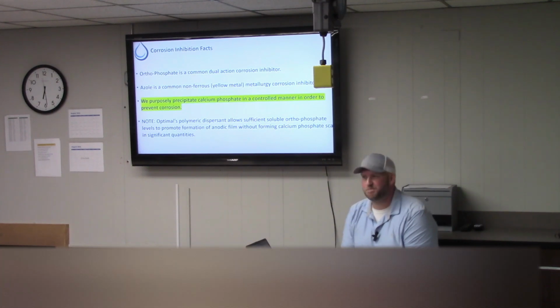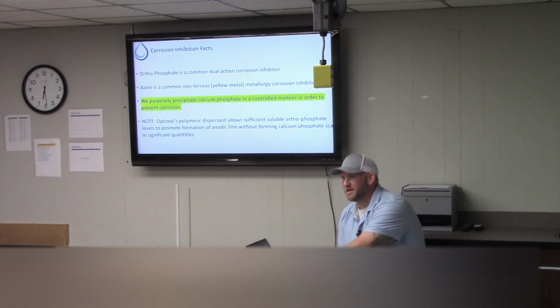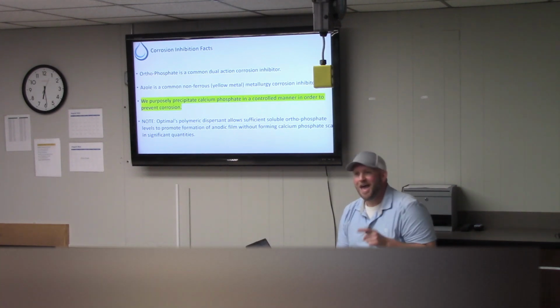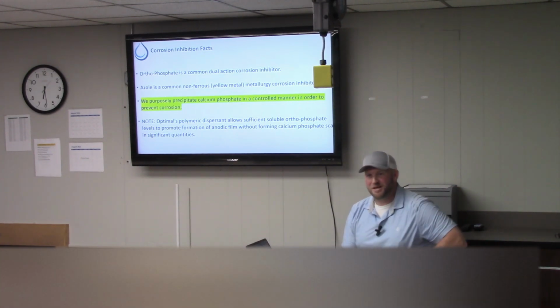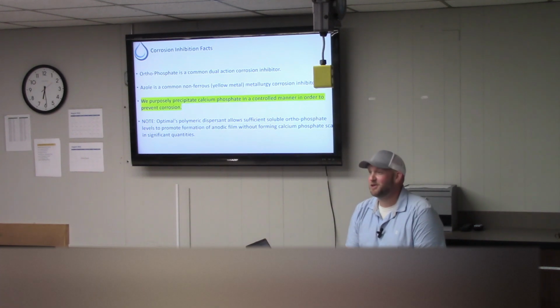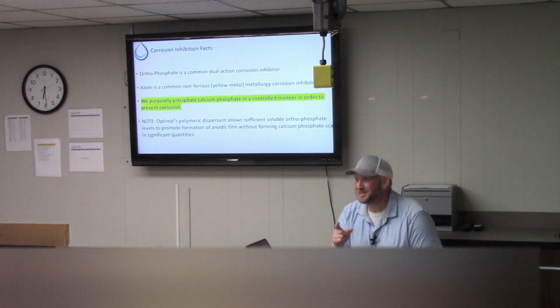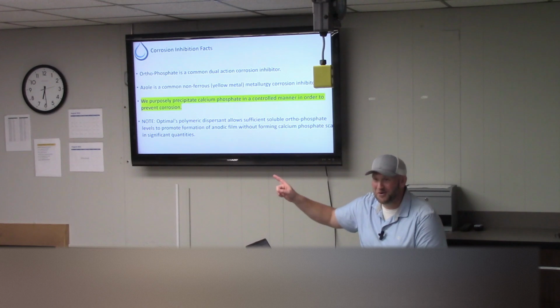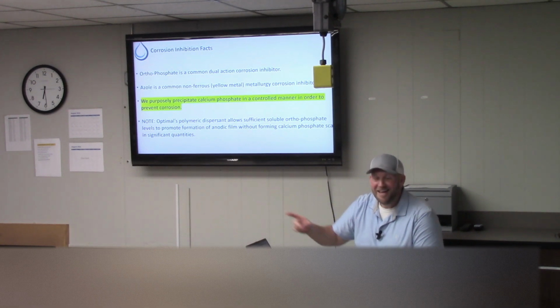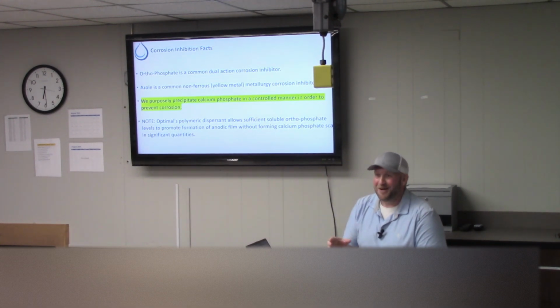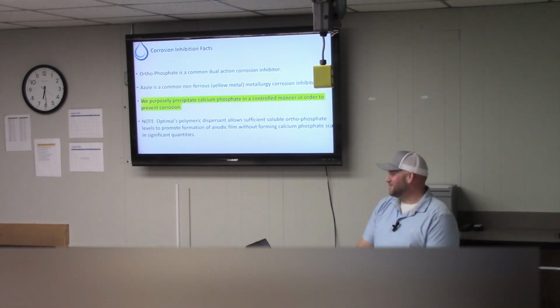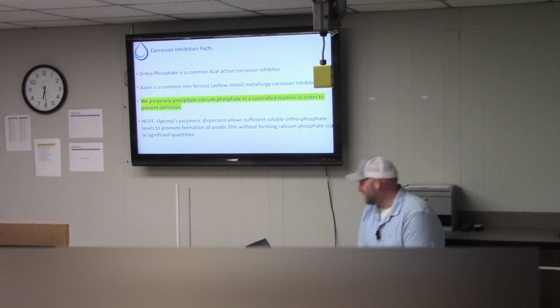They should not be pristine at the end of the year. You should have to do annual cleanings on your cooling tower. And if you do have a pristine basin, you should be asking yourself why, because all that schmooey is setting up somewhere in that system. You should figure out where before it figures it out for you. We can help with that as well—engage your water treatment experts in that conversation.